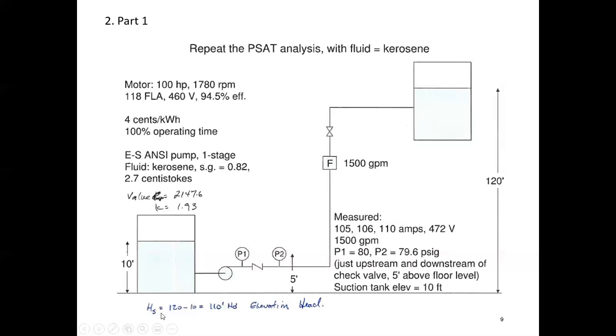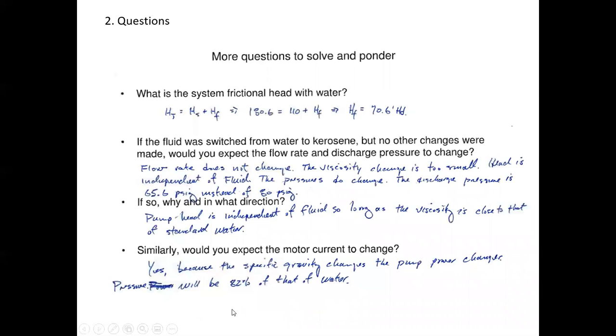I'm just noting here that the static head is 120 minus 10, which we already talked about. And so then the first point it asks is, what is the system frictional head with water? And well, it's the total head, 180.59 or 0.6 is equal to 110 plus the frictional head. And so you can just subtract 110 from this, and you get 70.6 feet of frictional head at that flow rate.